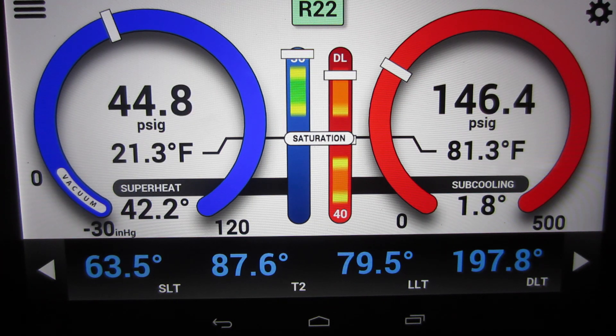The saturation temperature is 21, the suction line temperature is 63. That ain't bad — it's 76 out right now. That's not bad, but our superheat is 42.